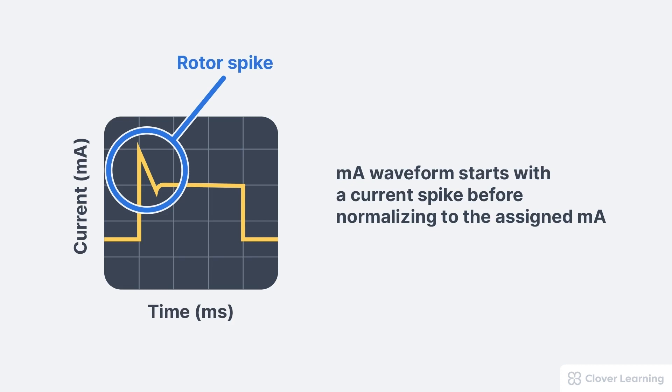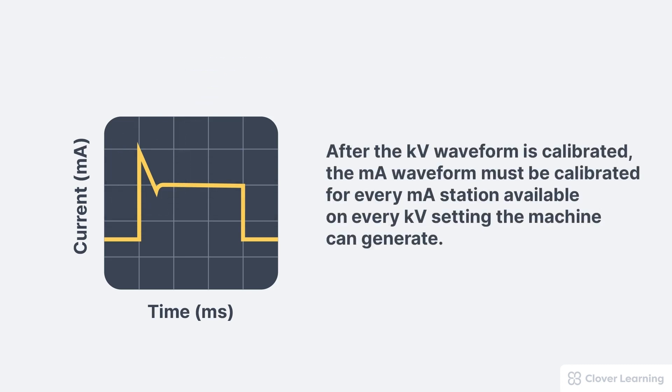After this rotor spike, the MA waveform should then be completely flat through the end of the exposure. After the KV waveform is calibrated, the MA waveform must be calibrated for every MA station on every KV setting.